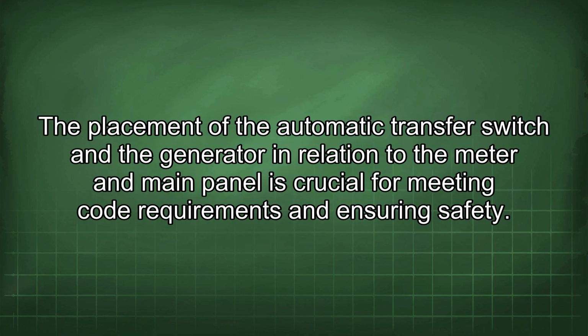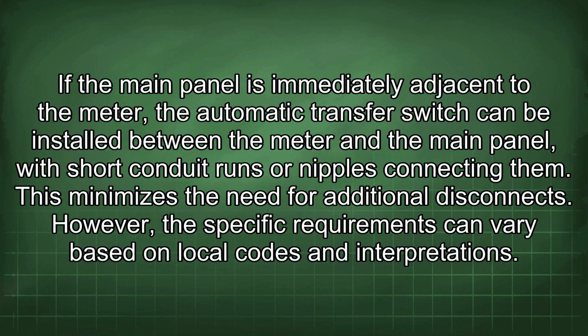The placement of the automatic transfer switch and the generator in relation to the meter and main panel is crucial for meeting code requirements and ensuring safety. If the main panel is immediately adjacent to the meter, the automatic transfer switch can be installed between the meter and the main panel, with short conduit runs or nipples connecting them. This minimizes the need for additional disconnects. However, the specific requirements can vary based on local codes and interpretations.